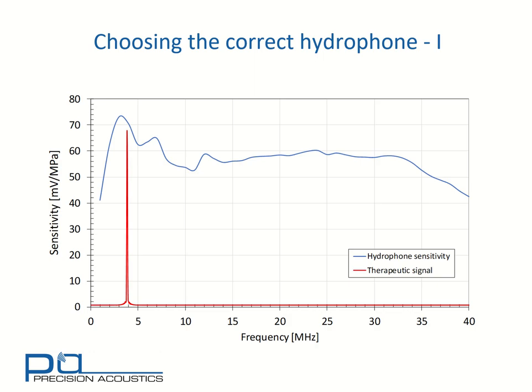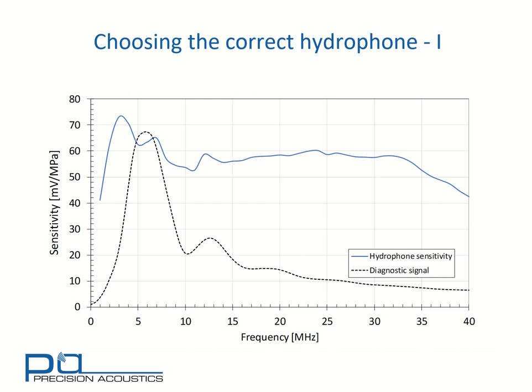It's important to make sure that we choose the correct hydrophone for these different applications. Considering the spectrum of the therapeutic signal with the needle hydrophone sensitivity — although we have some variation in the hydrophone's frequency response — within the very narrow band in which the significant energy for the therapeutic signal lies, there is actually very small variation. This would be an appropriate choice of hydrophone for this application. However, if we look at our diagnostic signal with its much broader spectrum, one can see that there's a lot of variation in sensitivity over that range, and the only way to correctly compensate for the frequency-dependent sensitivity variations would be to use deconvolution. We'll consider that in a further tutorial.